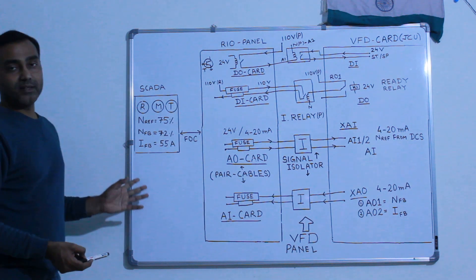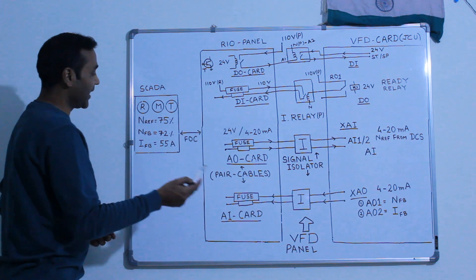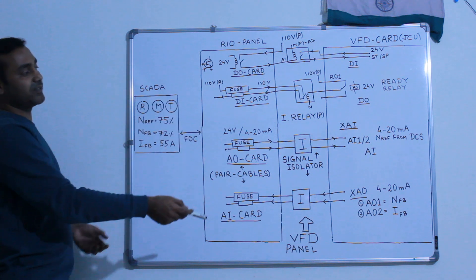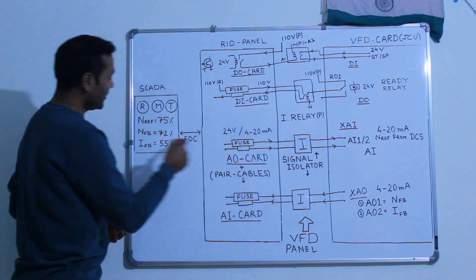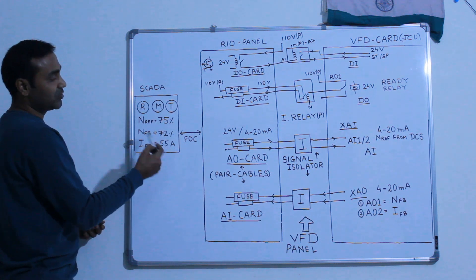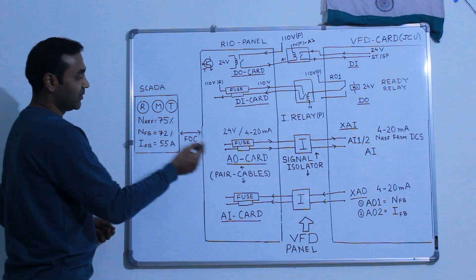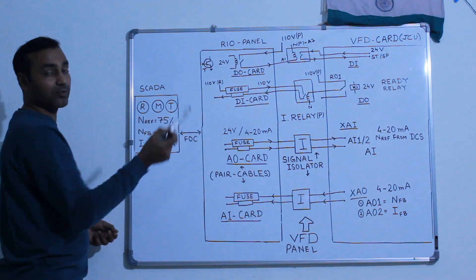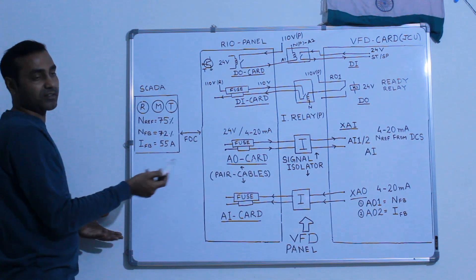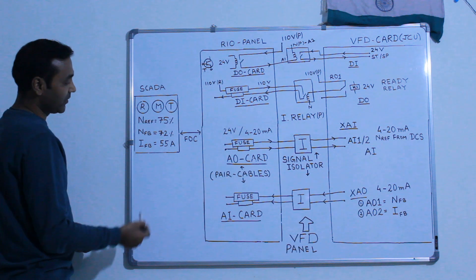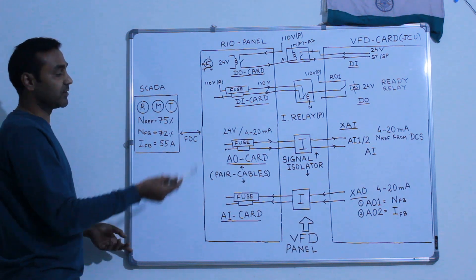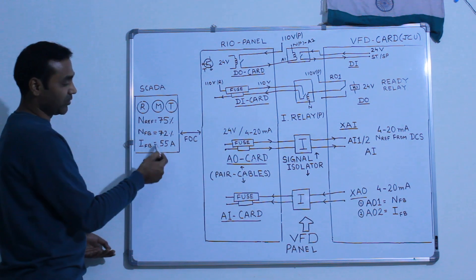If the operator is running that particular system manually, he will set a speed reference, for example we are taking 75%. Since the system is running, control room people will get two feedbacks - speed feedback, for example if the motor is given 75% but is not running at 75% because of load or unexpected issues, so 72% is coming. And current feedback - at how much current the VFD is trying to run that motor will also come back.